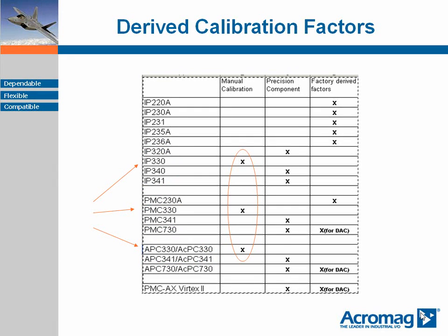The 330 series, which is available in four form factors, is calibrated in the factory by hand by adjusting the pot while the board is connected to a precision reference voltage. The other analog input boards are designed with precision resistor diode networks that are very stable and are validated against a precision reference voltage during test. This extra cost is offset by a low reject rate during final test and the elimination of operator intervention.